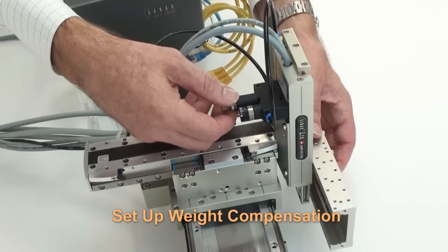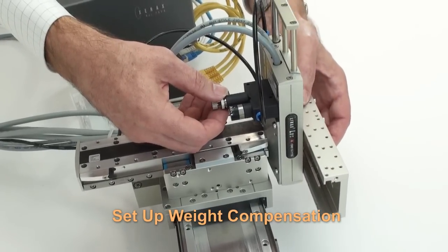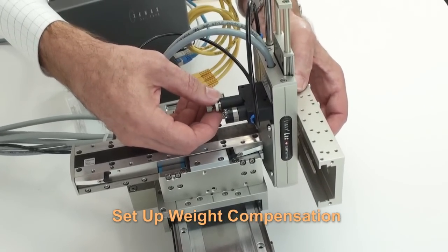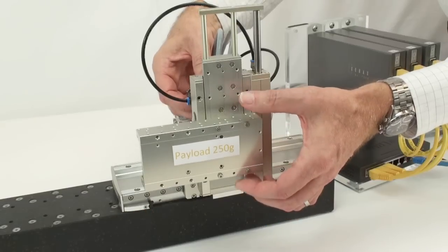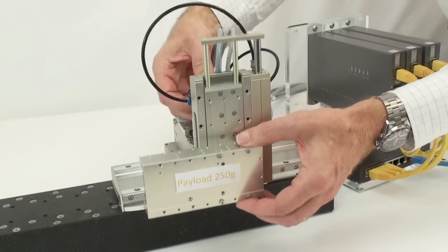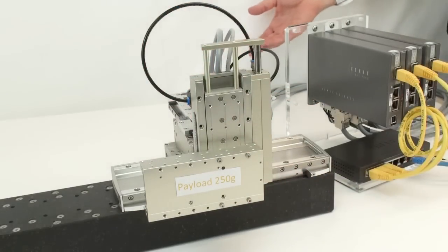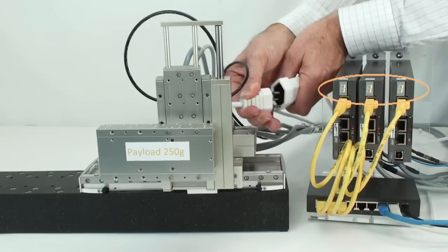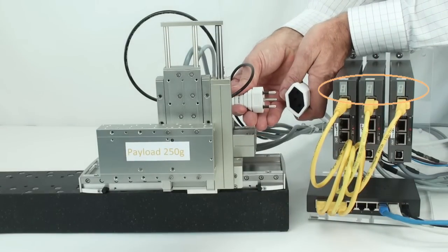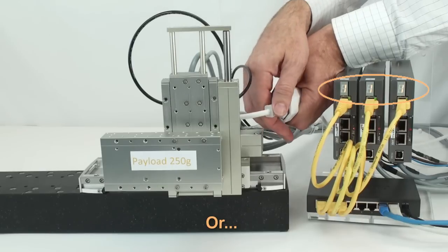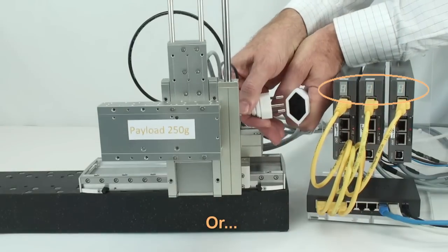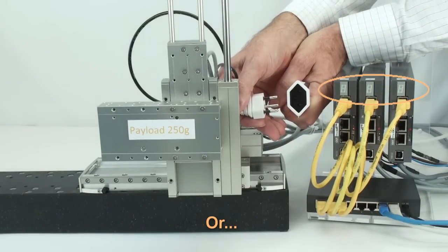First, we will adjust the optional weight compensation. As mentioned before, the weight compensation works with compressed air, but has no air consumption. With a commercial air pressure regulator, the compensation force can be adjusted. In case of power interruption, the carriage slider remains in position, like you see now. Or it moves upwards to the mechanical limit, depending on the air pressure regulator adjustment.